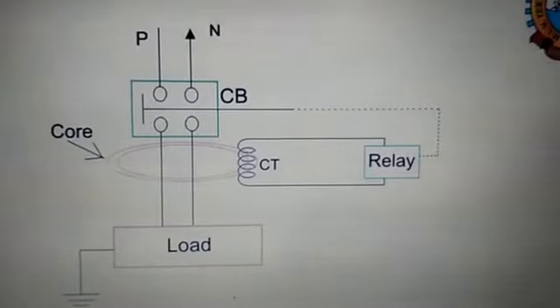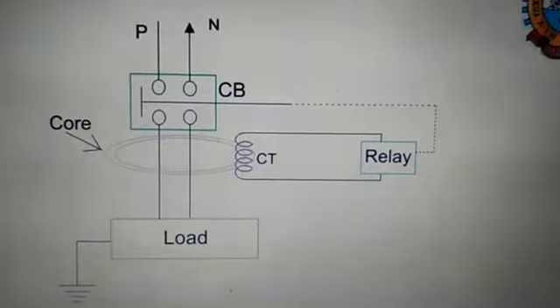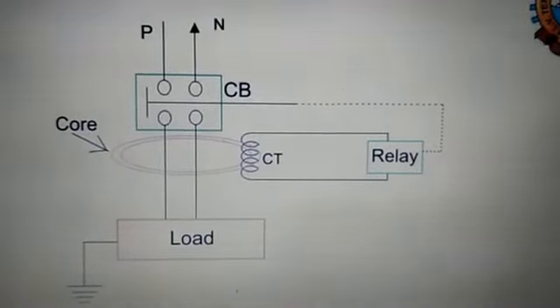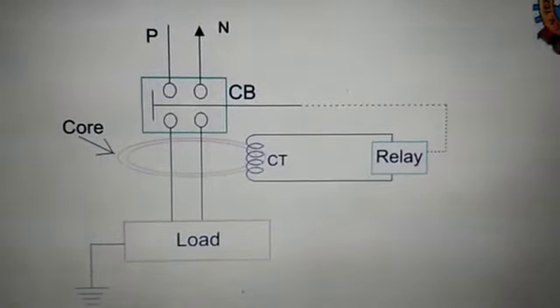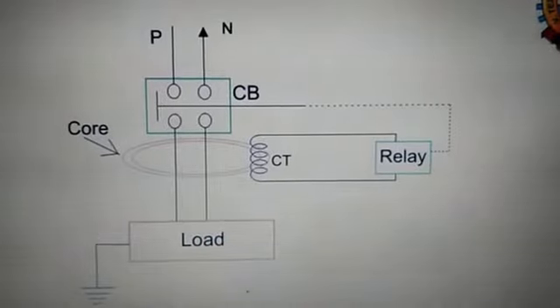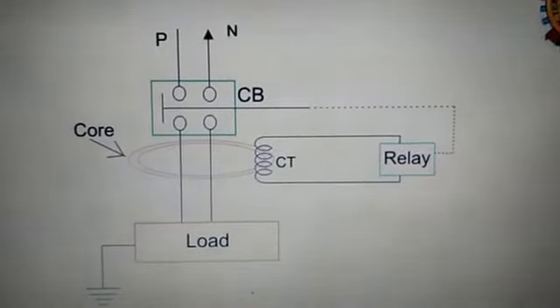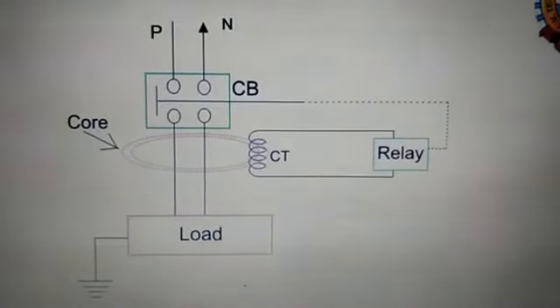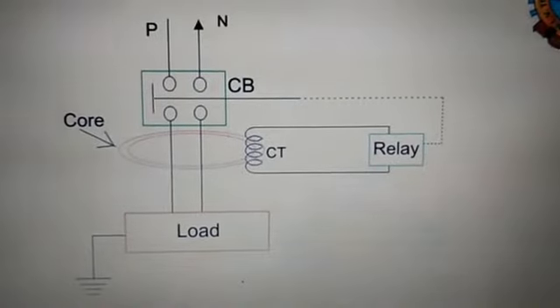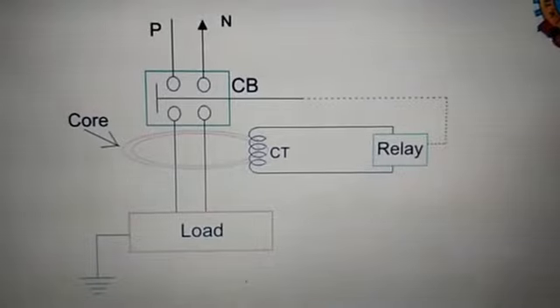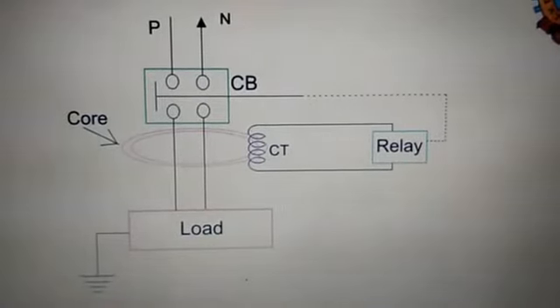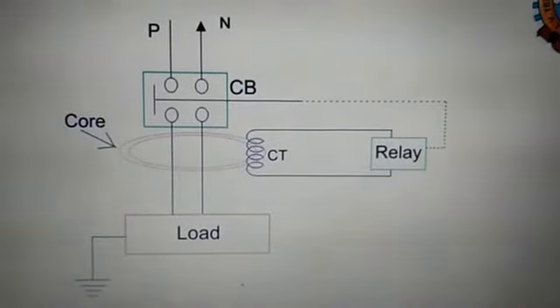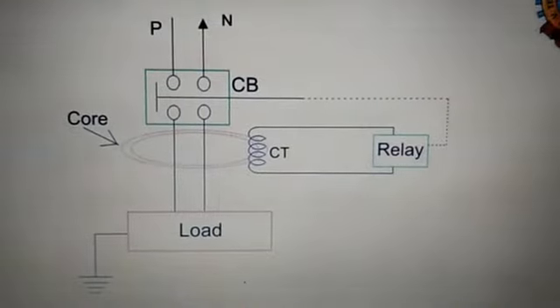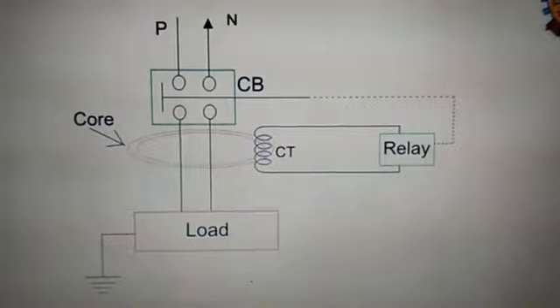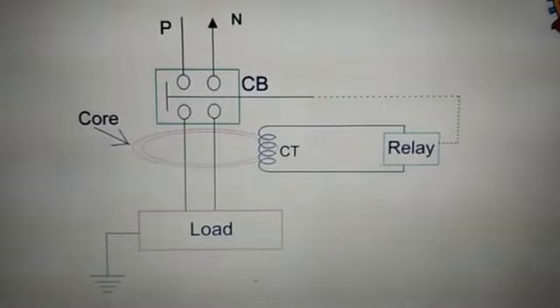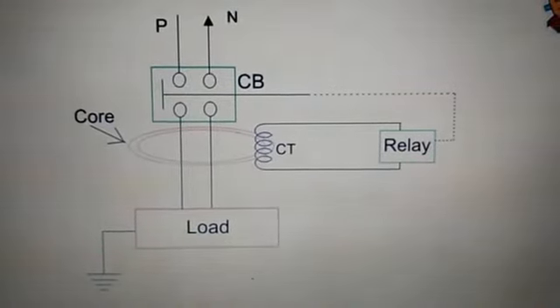The flow of current through the minor winding is 0 in the stable condition. In this condition, the flux due to the current over the phase wire will be cancelled by the current through the neutral wire. Meanwhile, the current that flows from the phase will be returned to the neutral. When any fault occurs, a slight current will run into the ground also. This creates an imbalance between the line and neutral current, and that makes an unstable magnetic field. This unstable magnetic field encourages a current flow through the minor winding, which is directly associated with the sensing circuit. Now this will detect the outflow and direct a signal to the tripping system.